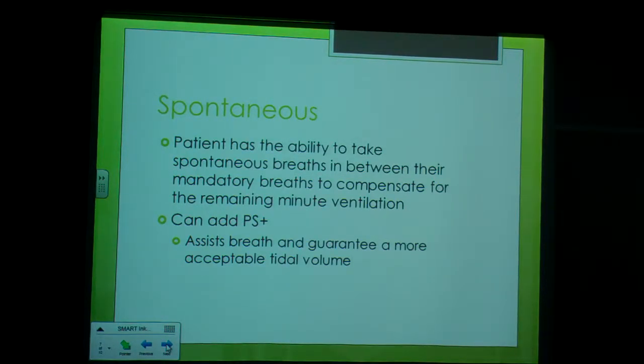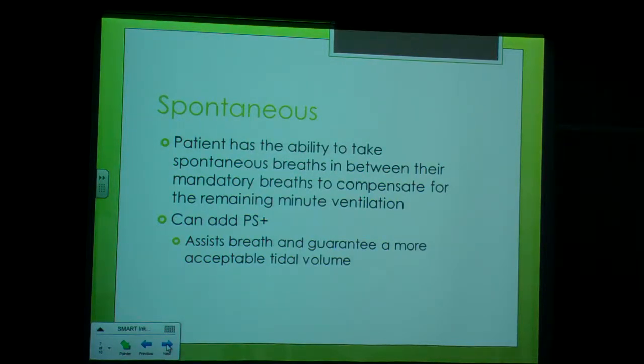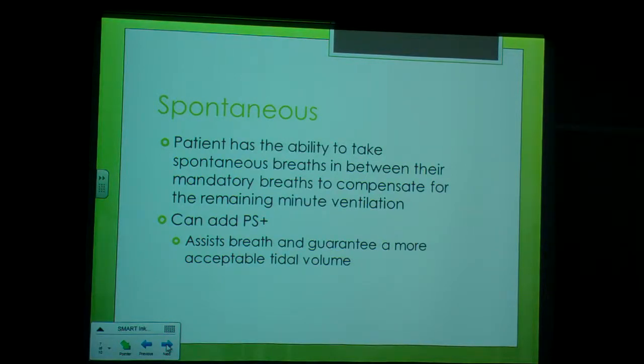On the spontaneous breaths, patients have the ability to take spontaneous breaths in between the mandatory breaths that are preset, which will compensate for the remaining minute ventilation. You can add pressure support as an option to the spontaneous breaths, which assists with the breaths and guarantees a more acceptable tidal volume, giving you a more acceptable minute ventilation as well.